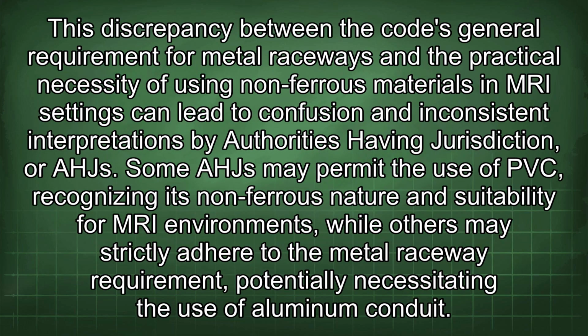This discrepancy between the code's general requirement for metal raceways and the practical necessity of using non-ferrous materials in MRI settings can lead to confusion and inconsistent interpretations by authorities having jurisdiction, or AHJs. Some AHJs may permit the use of PVC, recognizing its non-ferrous nature and suitability for MRI environments, while others may strictly adhere to the metal raceway requirement, potentially necessitating the use of aluminum conduit.